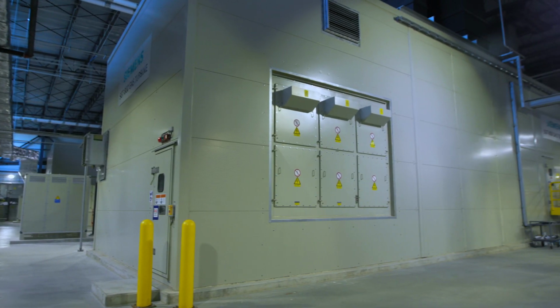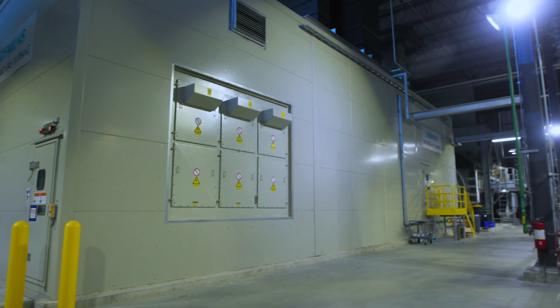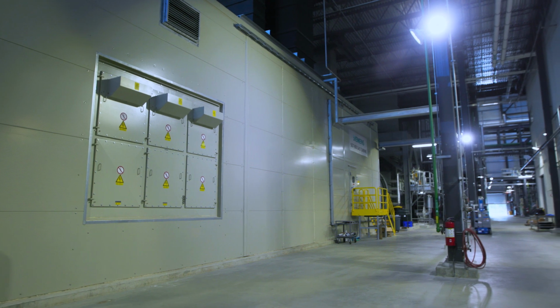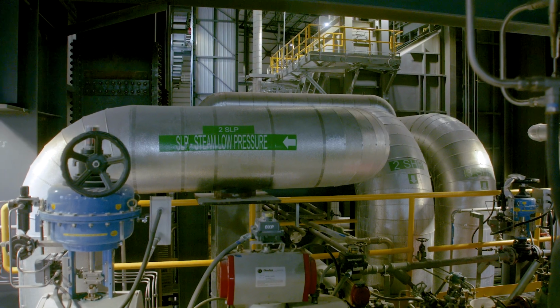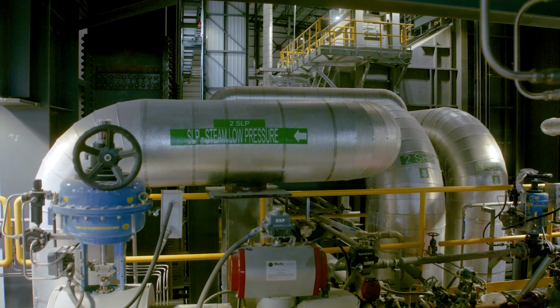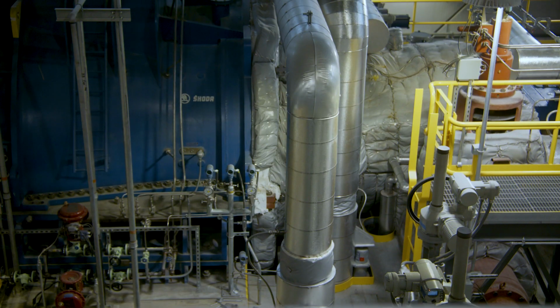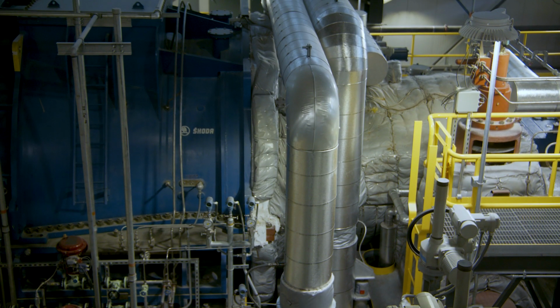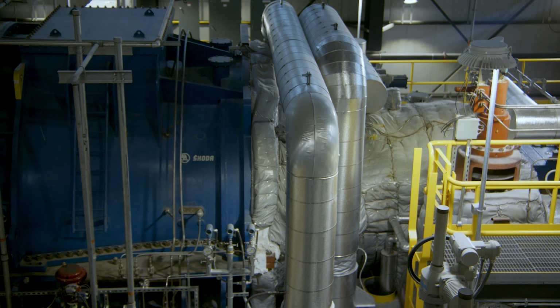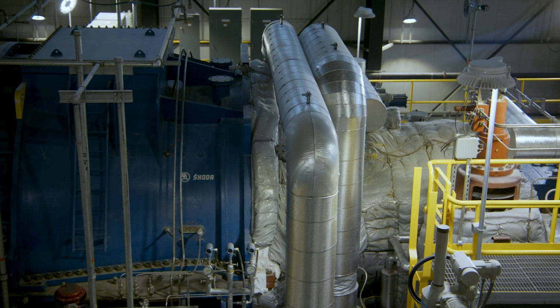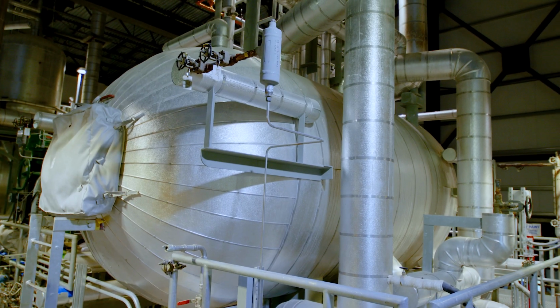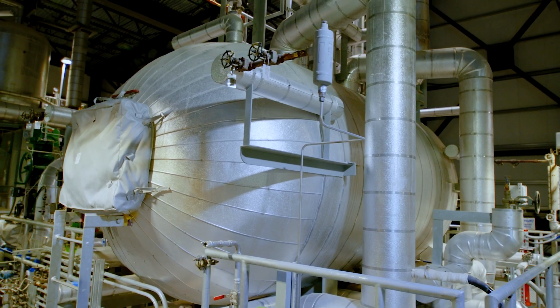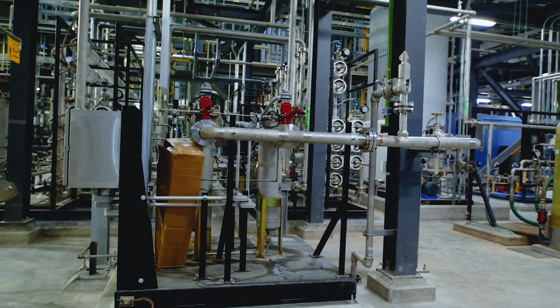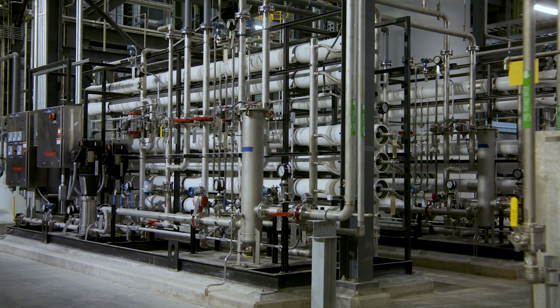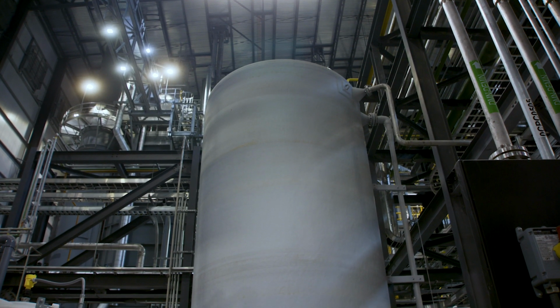The 2 primary combustion gas turbines are what's known as combined cycle units, meaning that the hot exhaust gas from the combustion gas turbines is used to produce high temperature and pressure steam from a heat recovery steam generator to drive a steam turbine generator. Each heat recovery steam generator can produce up to 280,000 pounds of steam. These HRSGs are also closed-loop systems, recouping close to 80% of the steam.